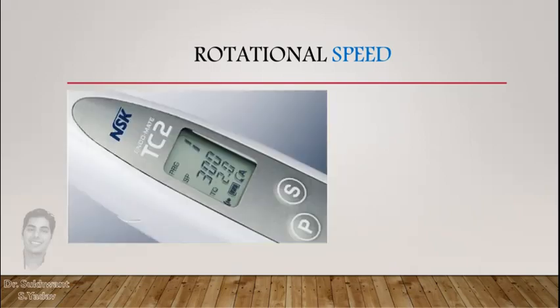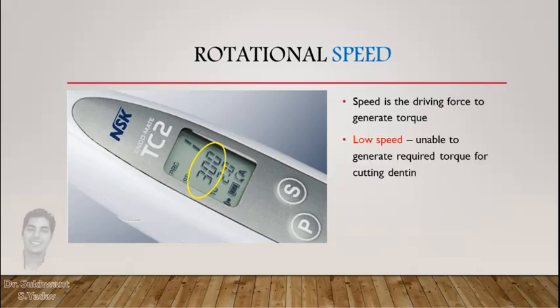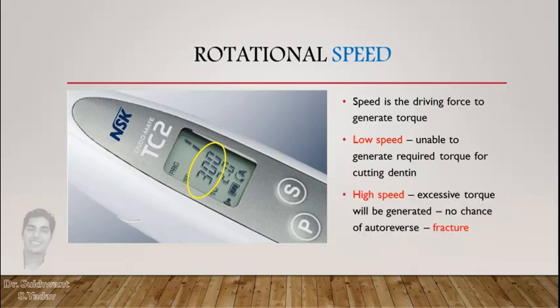Rotational speed is also important — speed is the driving force for generation of torque. If speed is lower than recommended, it will not generate enough torque to cut dentine. If speed is too high, excessive torque will be generated and that will not give the instrument a chance to auto-reverse when torque exceeds the safe limit, and the instrument can fracture.